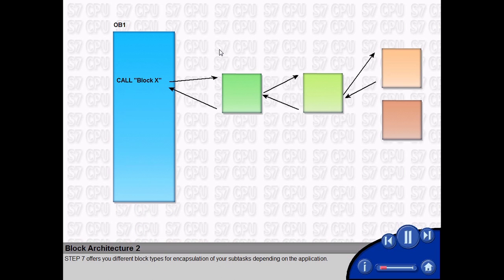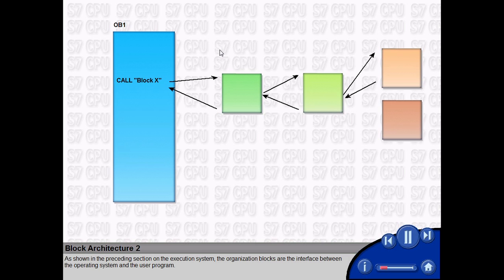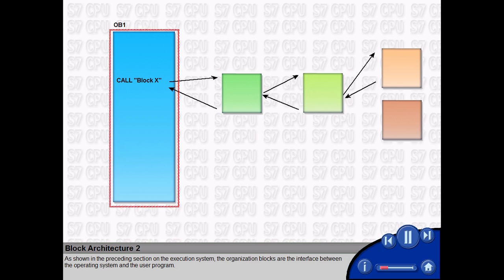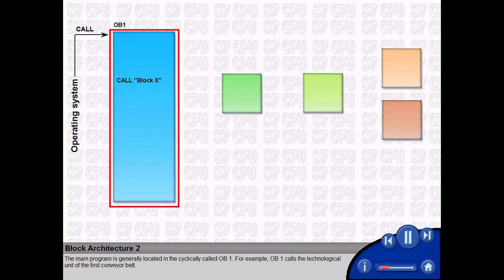Step 7 offers you different block types for encapsulation of your subtasks depending on the application. As shown in the preceding section on the execution system, the organization blocks are the interface between the operating system and the user program. The main program is generally located in the cyclically called OB1.